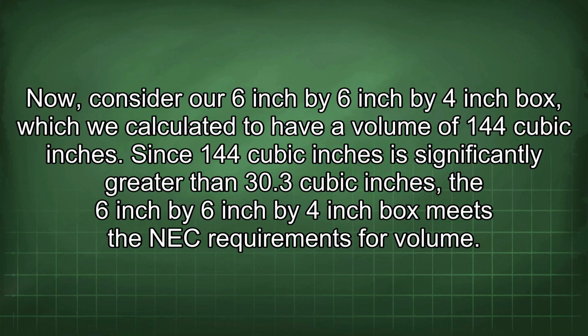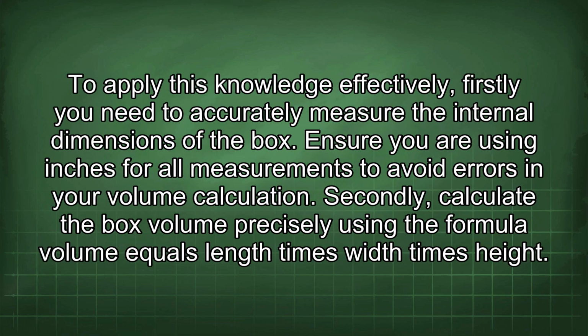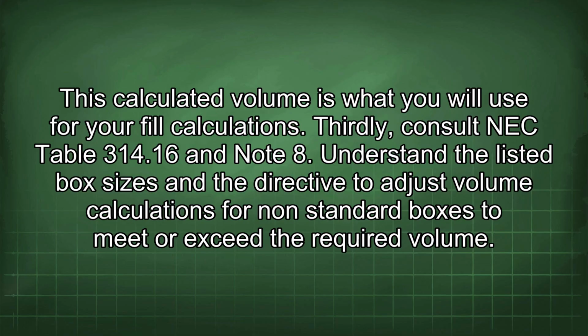To apply this knowledge effectively, firstly you need to accurately measure the internal dimensions of the box. Ensure you are using inches for all measurements to avoid errors in your volume calculation. Secondly, calculate the box volume precisely using the formula volume equals length times width times height. This calculated volume is what you will use for your fill calculations.